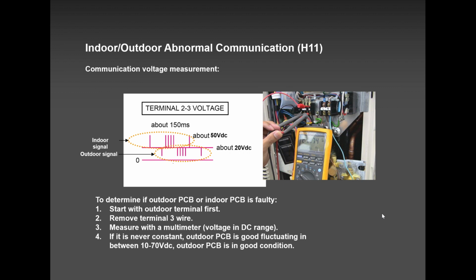Please do not use an amp probe. I keep repeating this because I had a problem with one guy using an amp probe and the meter wasn't fluctuating enough. And then we concluded that the outdoor PCB was bad, but we made a wrong diagnosis because the meter that was used was this amp probe. So please use this meter here that you can see for H11 codes, for measuring thermistors, sensors. Please use this multimeter, please. They give you good results. And if you don't have this meter, invest in one. They are not expensive for the money you are making. So please, amp probe for amps, multimeter for H11 error codes and sensors.